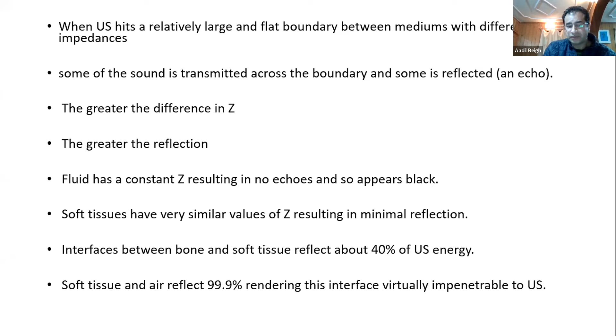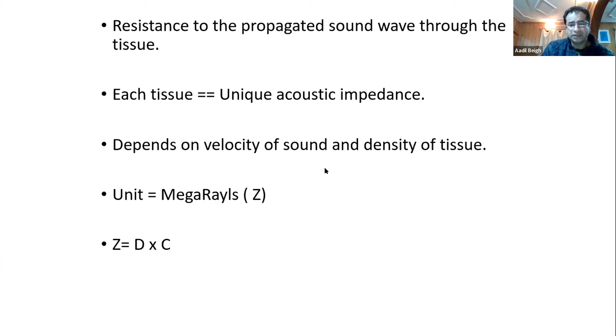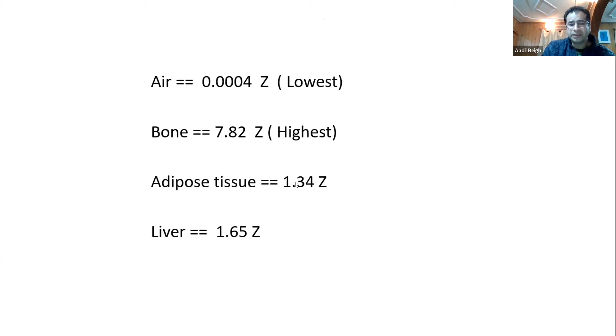Acoustic impedance is the resistance to the propagated sound waves through the tissue. Each tissue has a unique acoustic impedance. It depends on the velocity of the sound and the density of the tissue. Its units are megarayls. So the acoustic impedance is equal to the density of the tissue times the velocity of the sound. Air has the least acoustic impedance and bone has the highest. In between, there are adipose tissue, liver, and other tissues, which have impedance between 1.3 and 1.7.